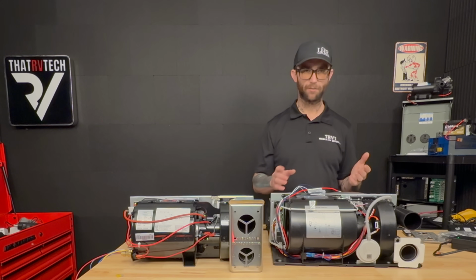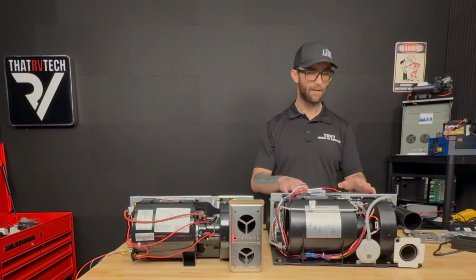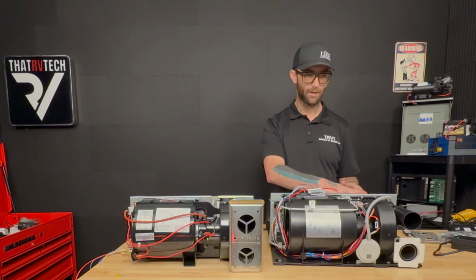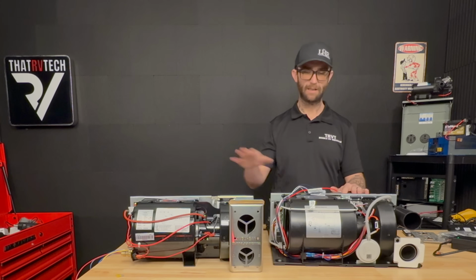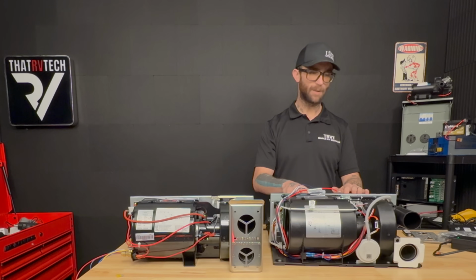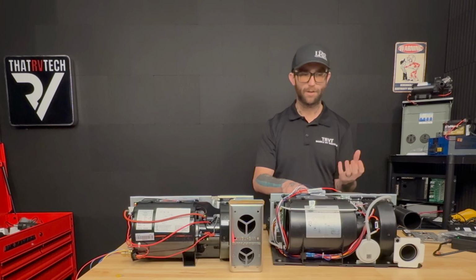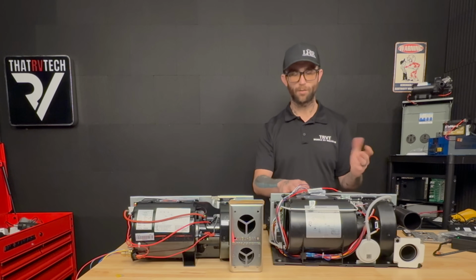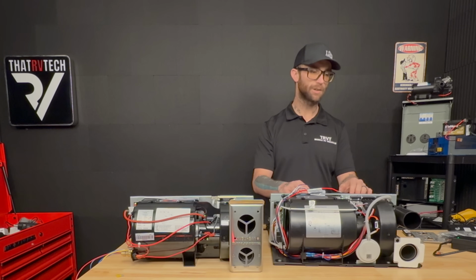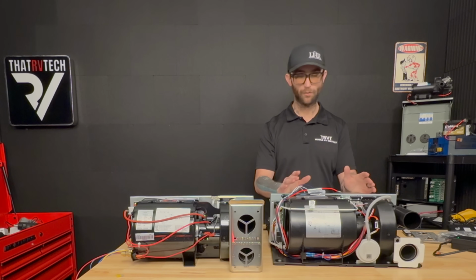I actually questioned for a second there whether or not it was lit, which is why I was touching the heat exchanger, because it was just a weird process to me. It's not what I'm used to. Typically that sag down during ignition is because of low voltage or a loose connection or something like that, causing low voltage during the ignition cycle.